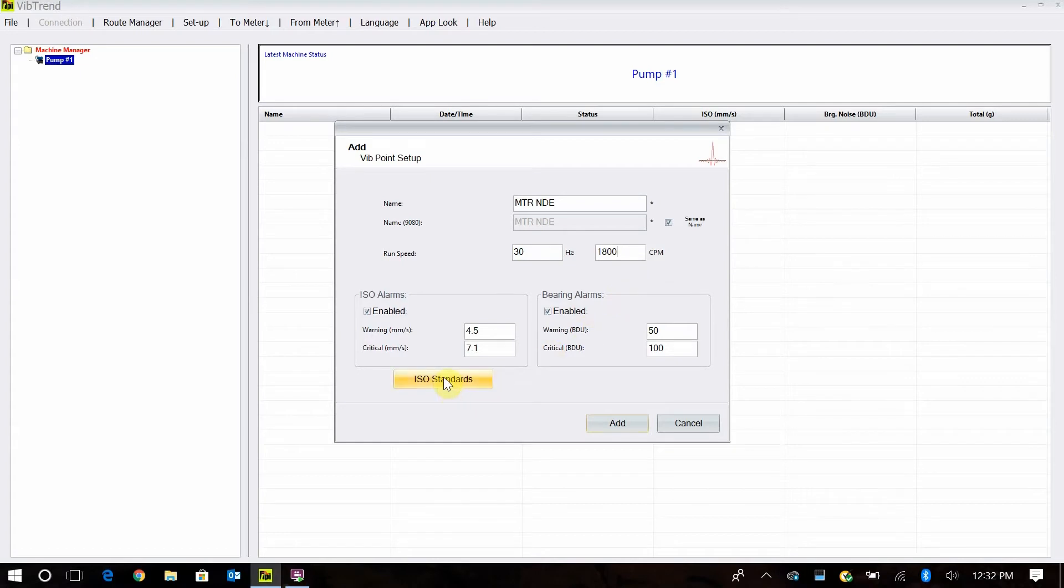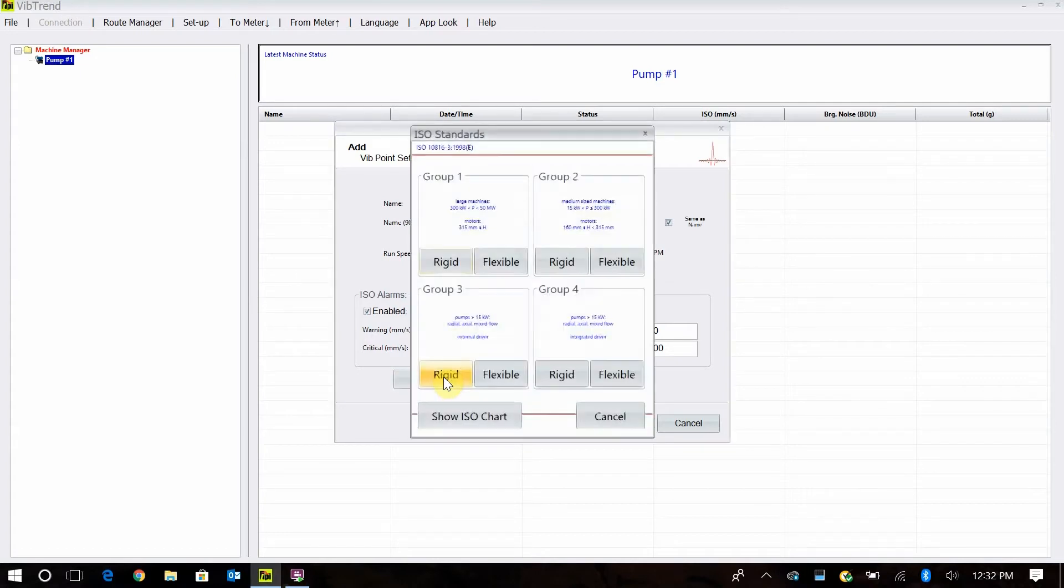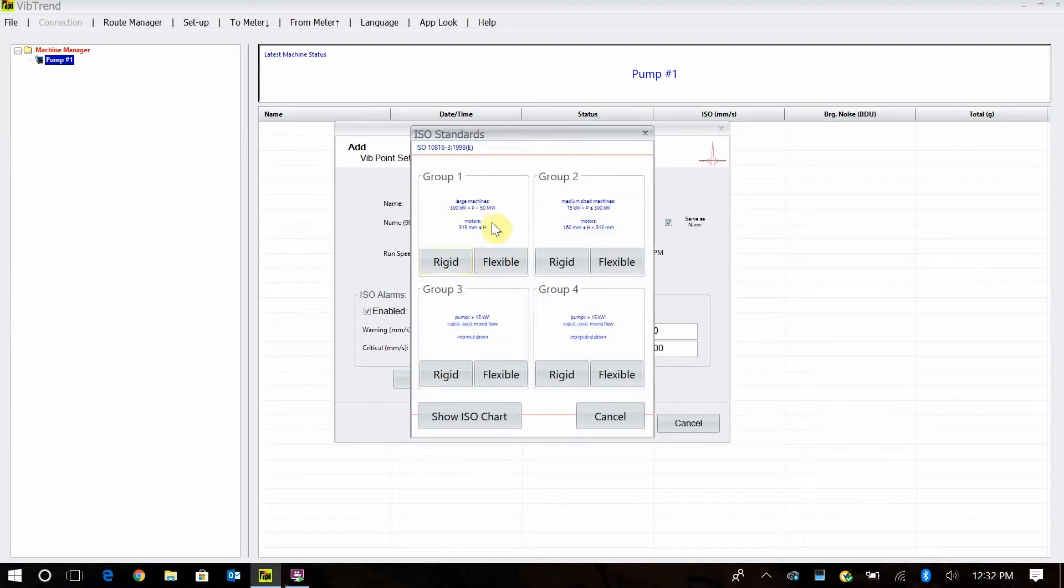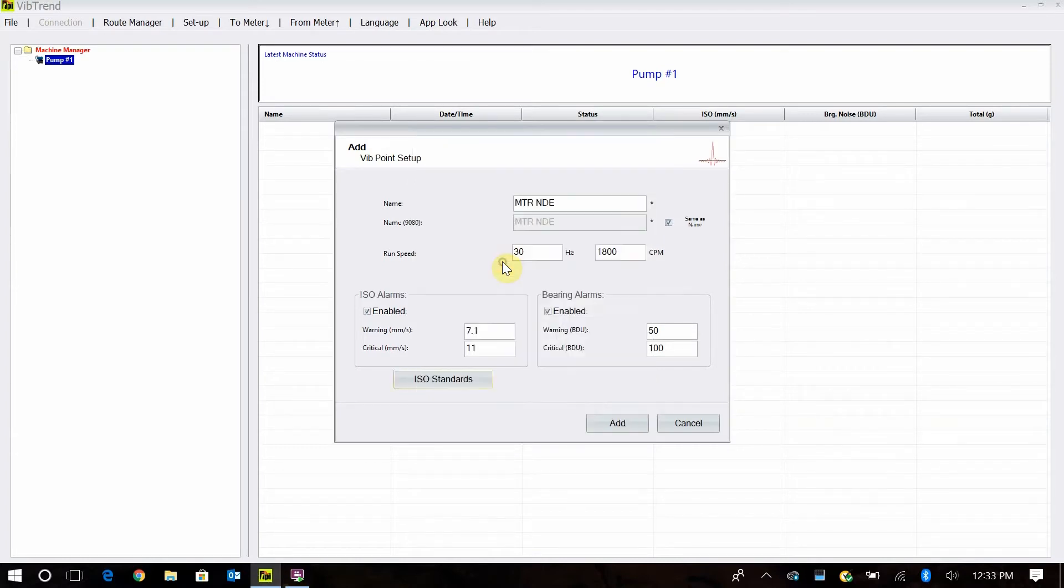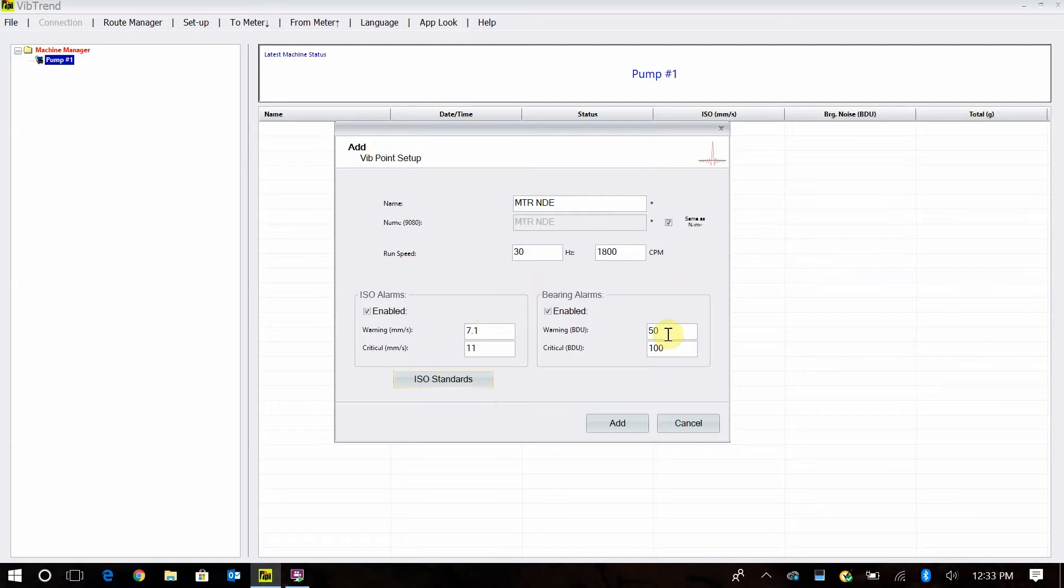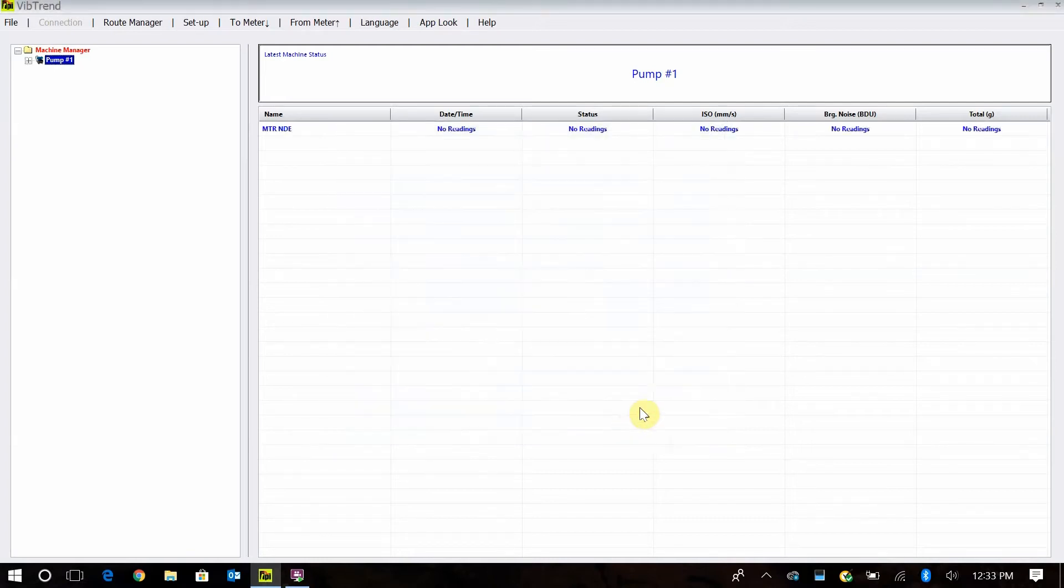Then I set my ISO standards or my ISO alarms. Right here we have a group one flexible, group two, group three. Usually starting off in the facility, if I don't have a vibration program or my machines are running a little rougher, I set everything to group one flexible. There you can see the values and everything right there in millimeters per second. My bearing damage units are set at 50 and 100. This is a good place to default or start with your bearing damage units. And then I simply say add.